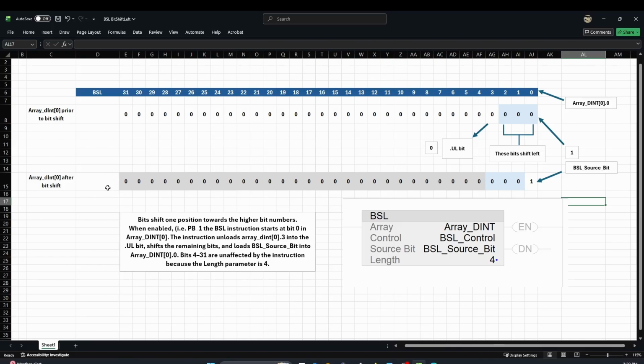So it's a beauty way of having like a sensor being tripped and then keeping track of where that box or item is on a conveyor. And then when it gets to a certain bit that we know corresponds to a pneumatic pusher or something like that, we can use that pneumatic pusher to push the box off. And we know exactly when the box is going to be there based on when those 1s are transferring along this array here. Okay, so let's create a program, guys, and let's see the basics of this, and then we're going to build up to that example where we have a sensor being tripped off and the pneumatic pusher pushing something off of a conveyor.